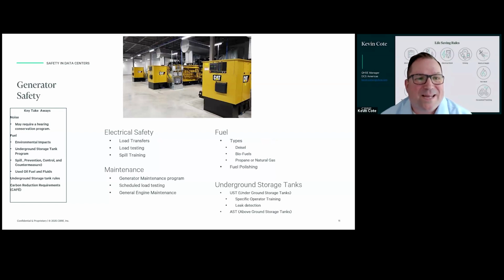Generators. So you have generators. These are very, very large generators, typically on site. So some of the electrical safety things that I pointed out would be load transfers. So what happens when the power goes out and that load is transferred? Load testing. As we are doing maintenance, we also do load testing. Generally, I believe it's about 35% of the load tested monthly. And then once a year, they do, I think, 90 to 100% load capacity on the generators to make sure that they can hold that load and that there aren't any defects.